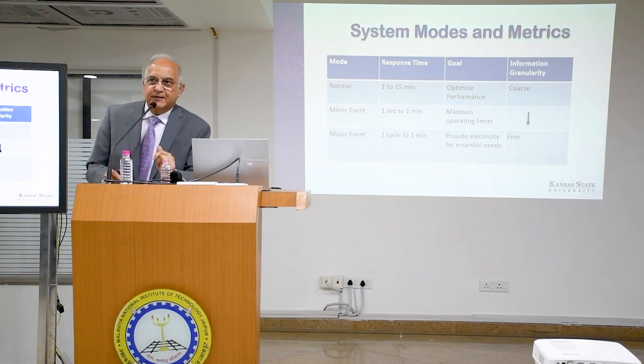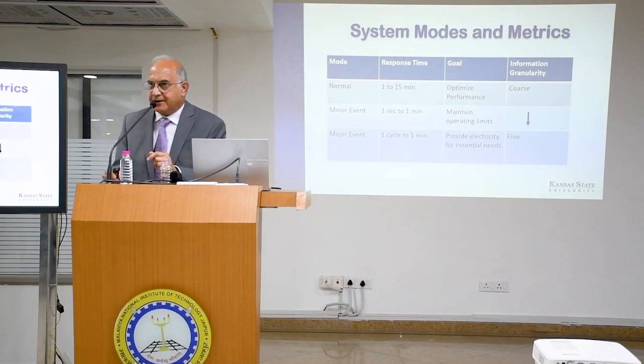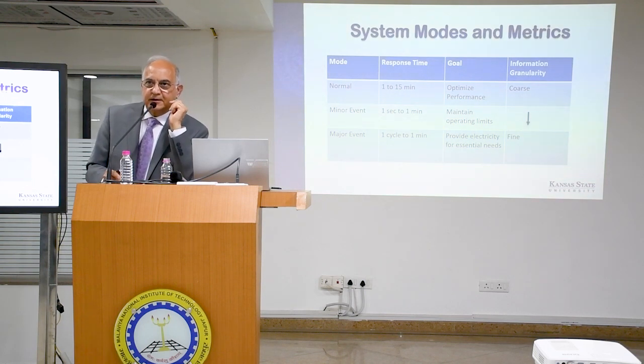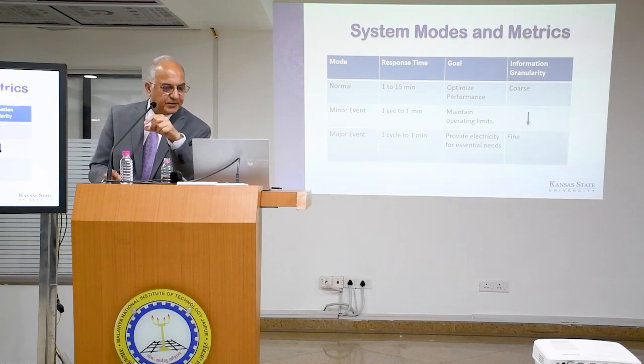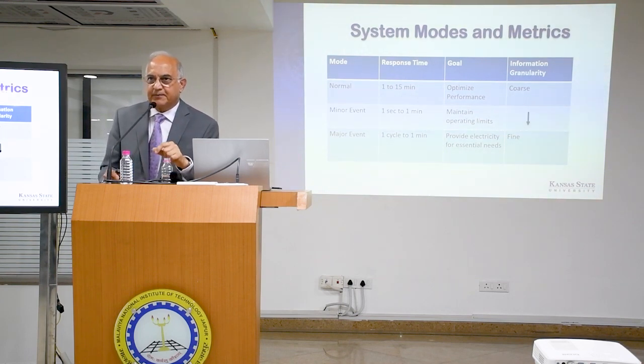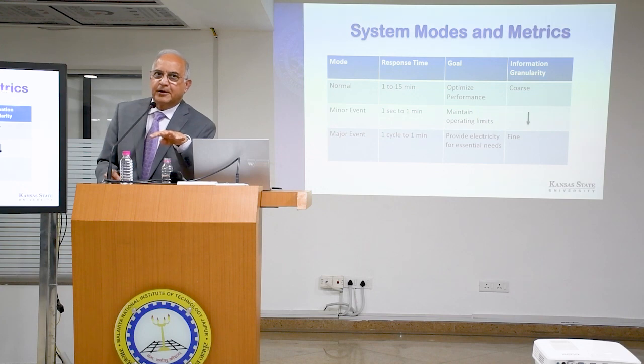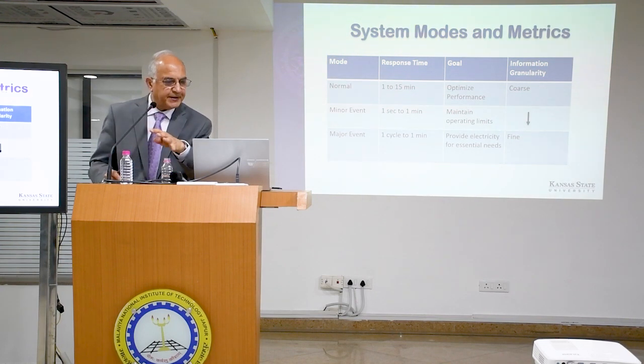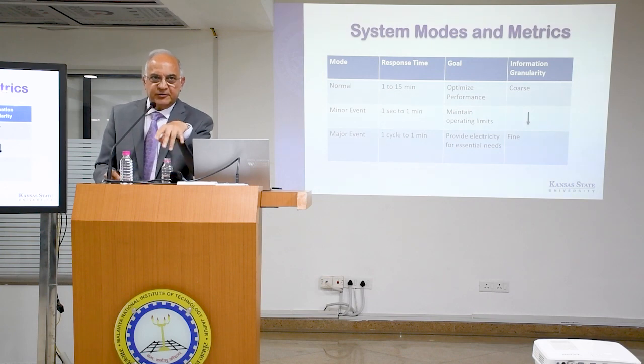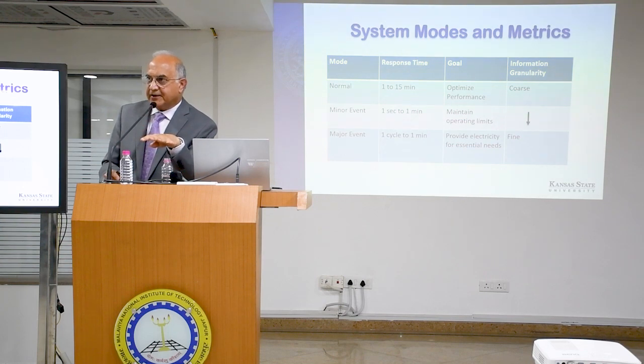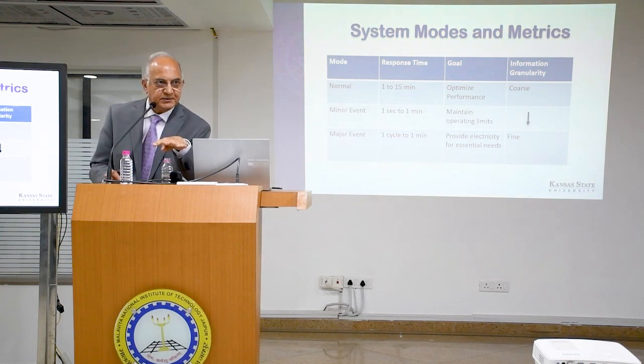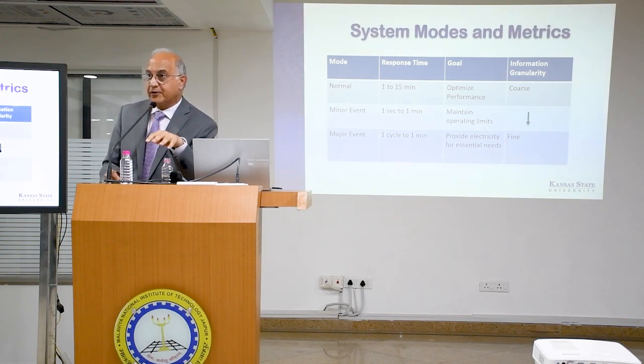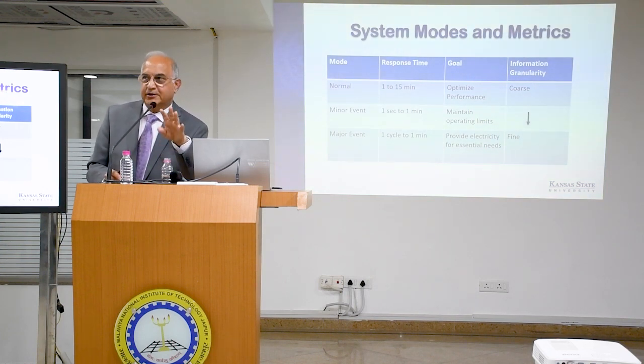On the other hand, if there is an event which is called a minor event, such as fluctuations happening in PV, you have to worry about things in a 1 second to 1 minute time frame because things are changing fast. In that case, you don't worry about optimizing, but you worry about maintaining the operating limits. And you need some more information compared to the case where things are not changing.